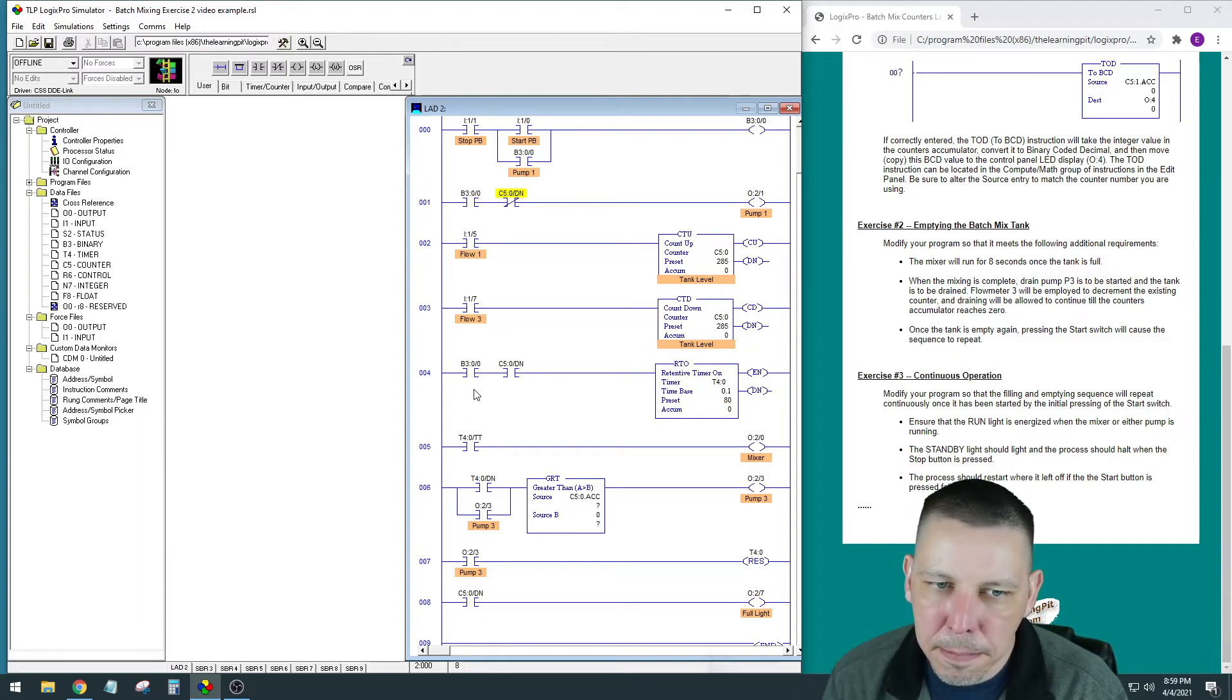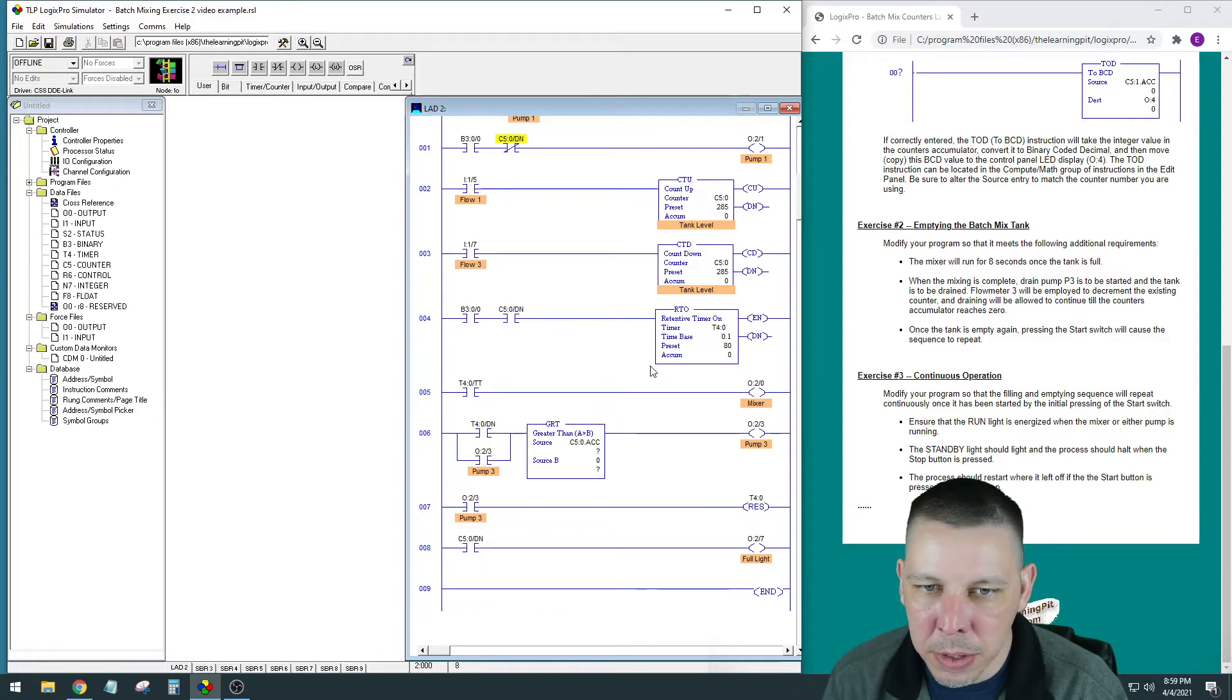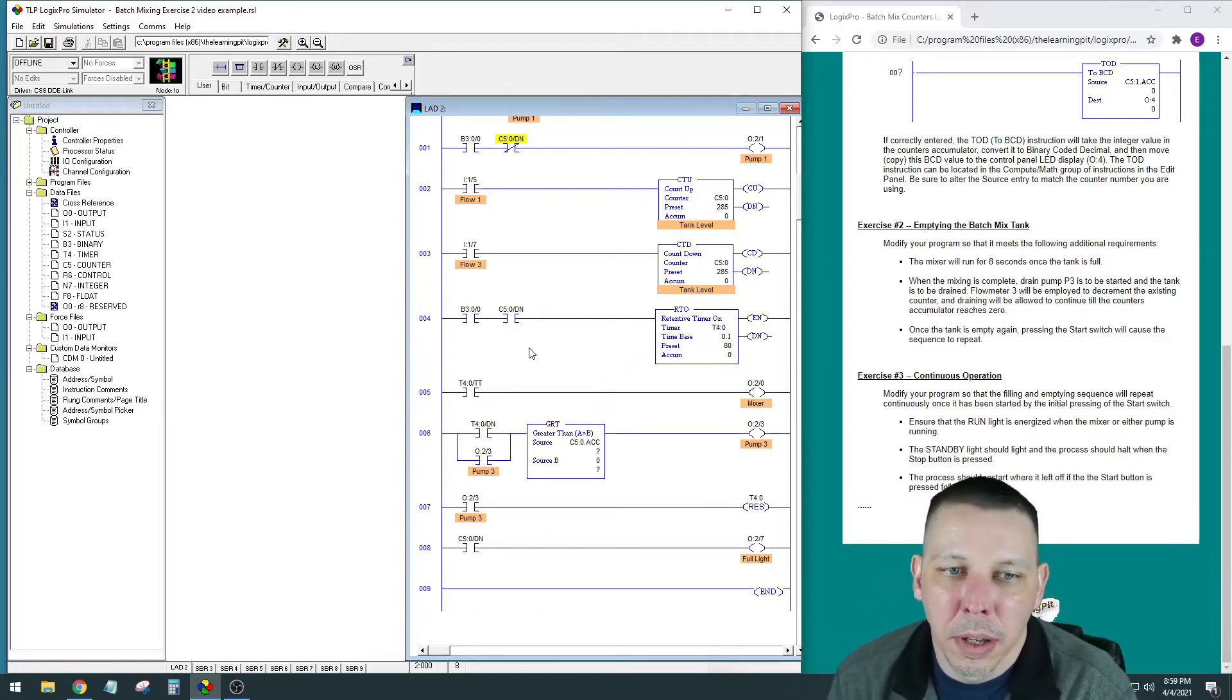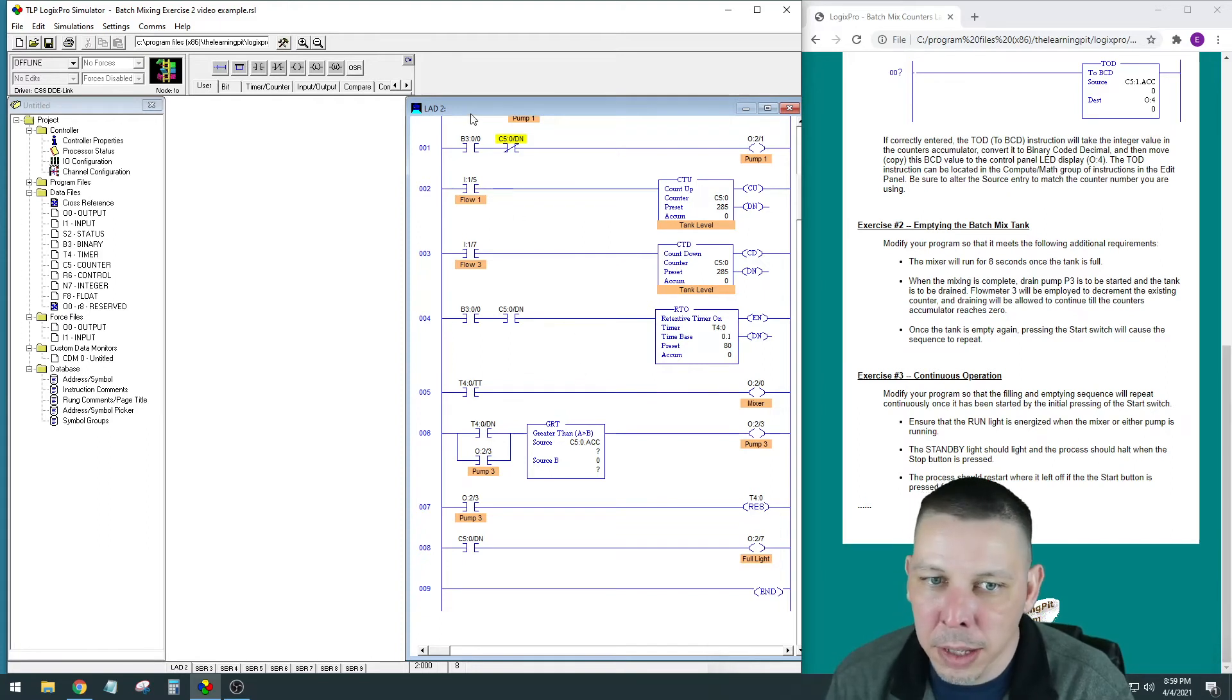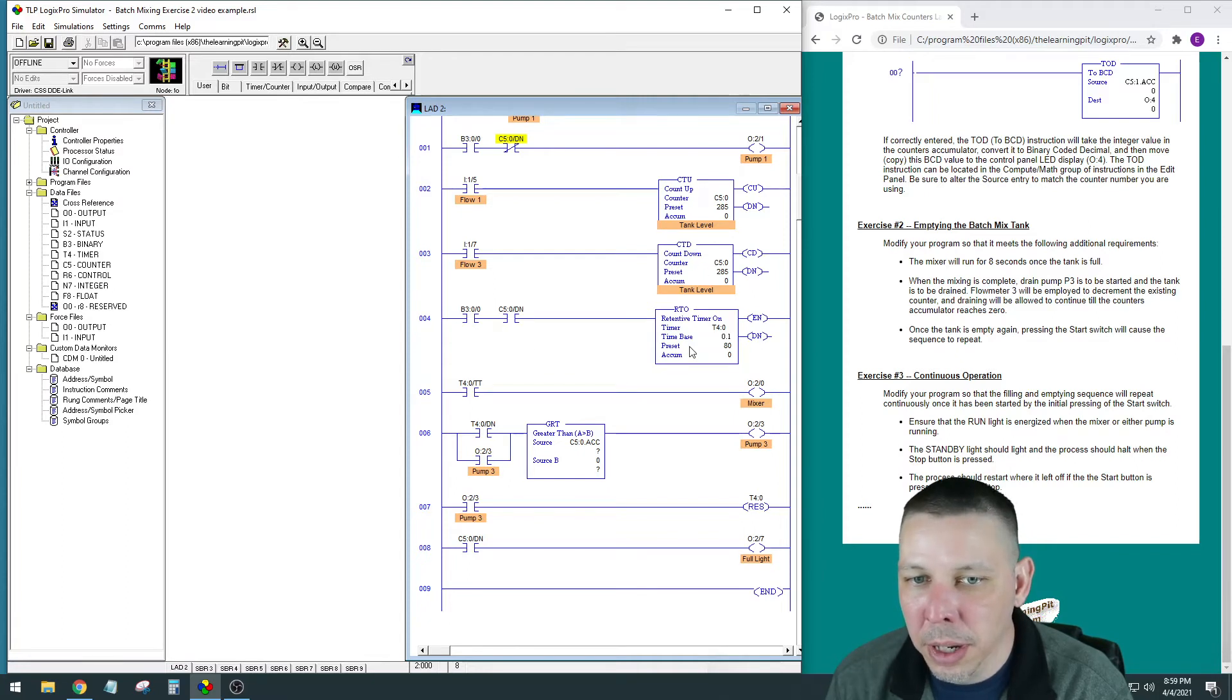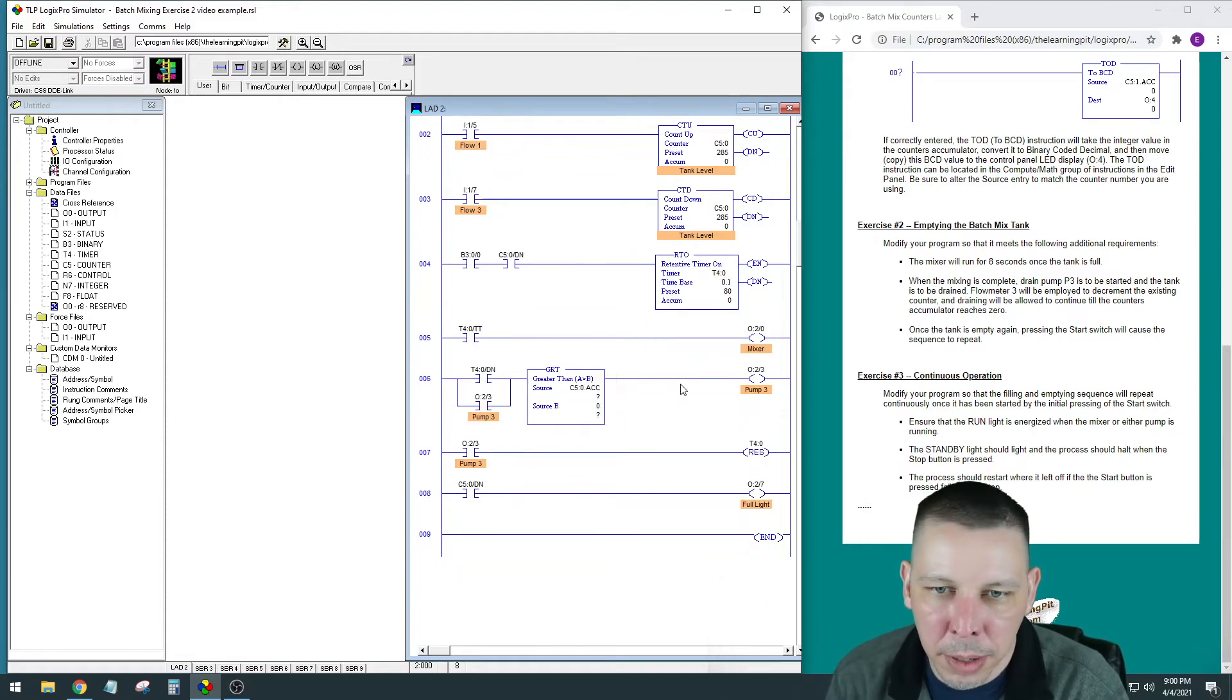Wait, is that right? I might not be able to use—I'm going to have to rearrange some other stuff here. C5.0 done bit—oh yeah, for my mixing. I was getting confused, I was thinking about the pumping out. Yeah, so this is the timer for the mixer, so we'll stop the mixer. If we hit stop, it'll be at 4 seconds here. When we hit start again, it'll enable this bit again. The counter above will still be done because the tank will still be full, and it'll pick up at 4 and go to 5, 6, 7, 8. So it won't restart the timer every time—it'll just pick up right where it left off.